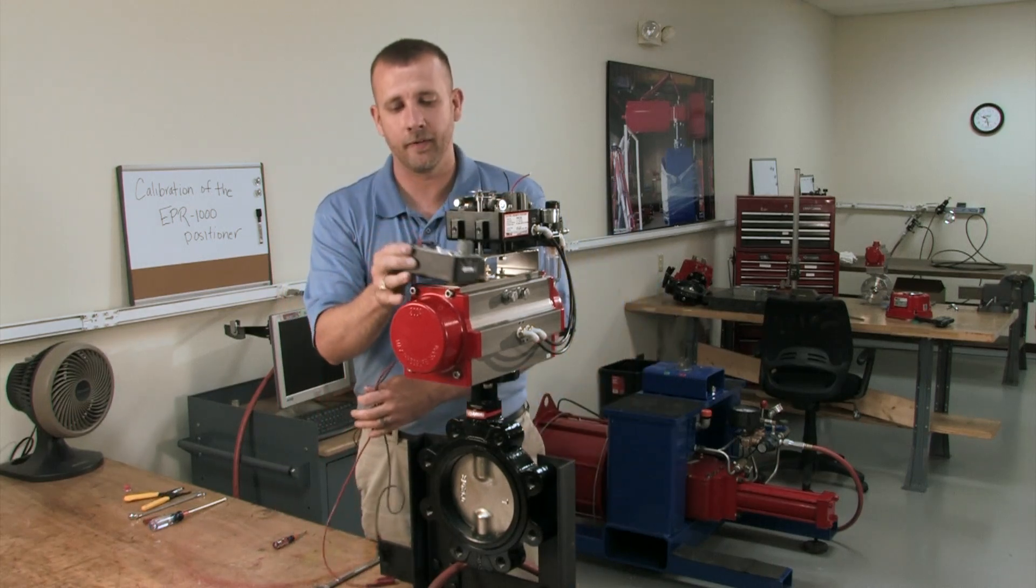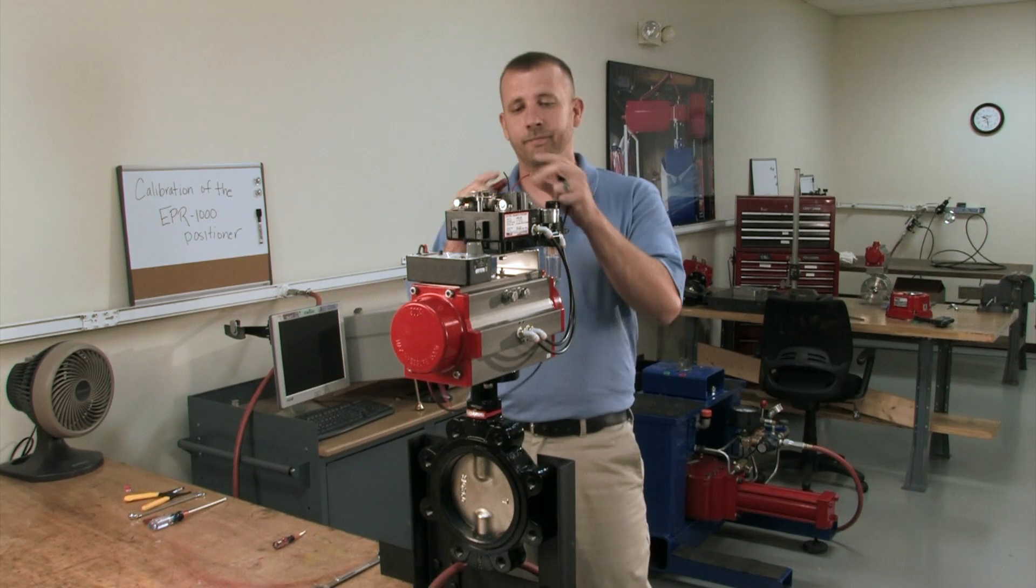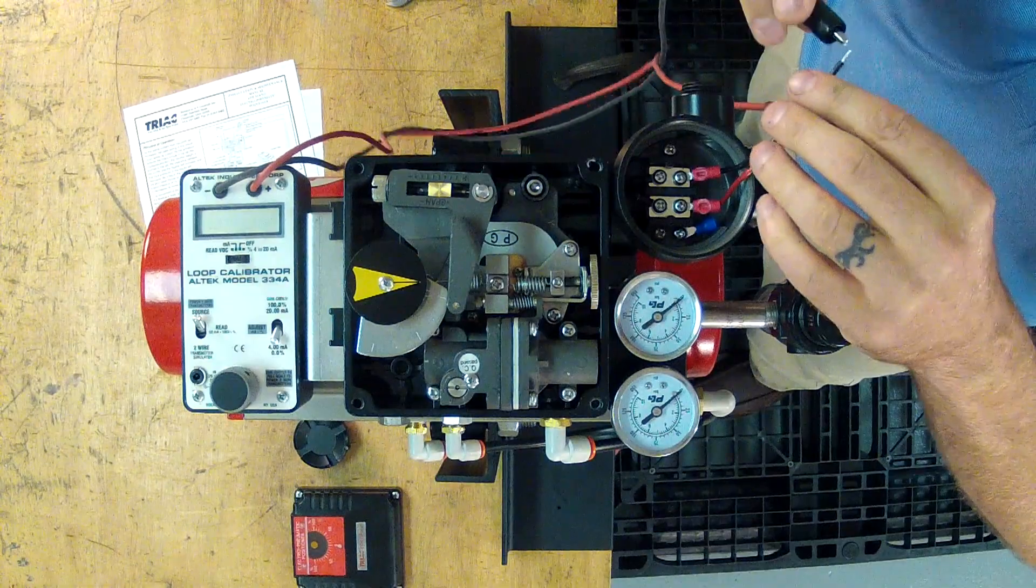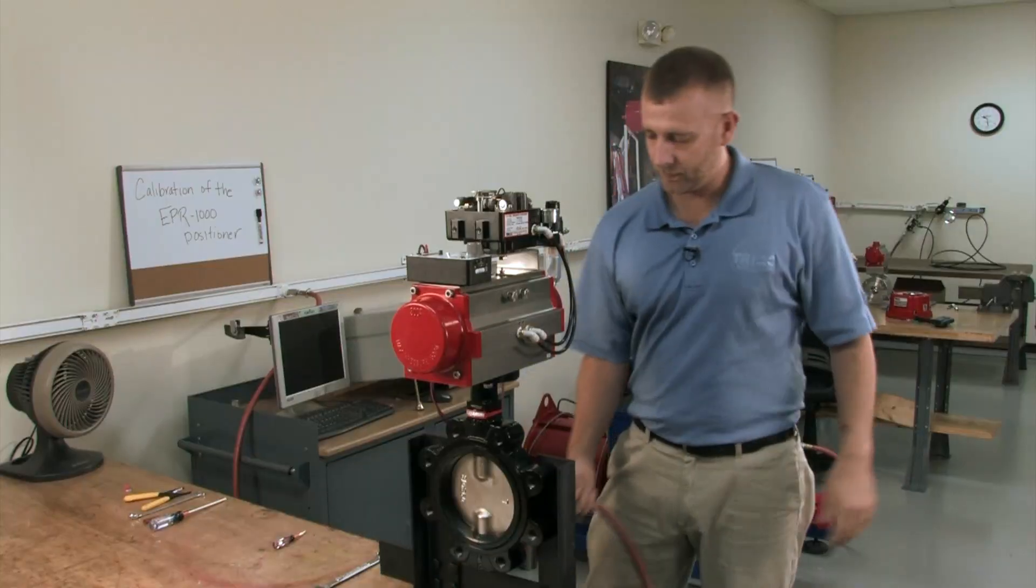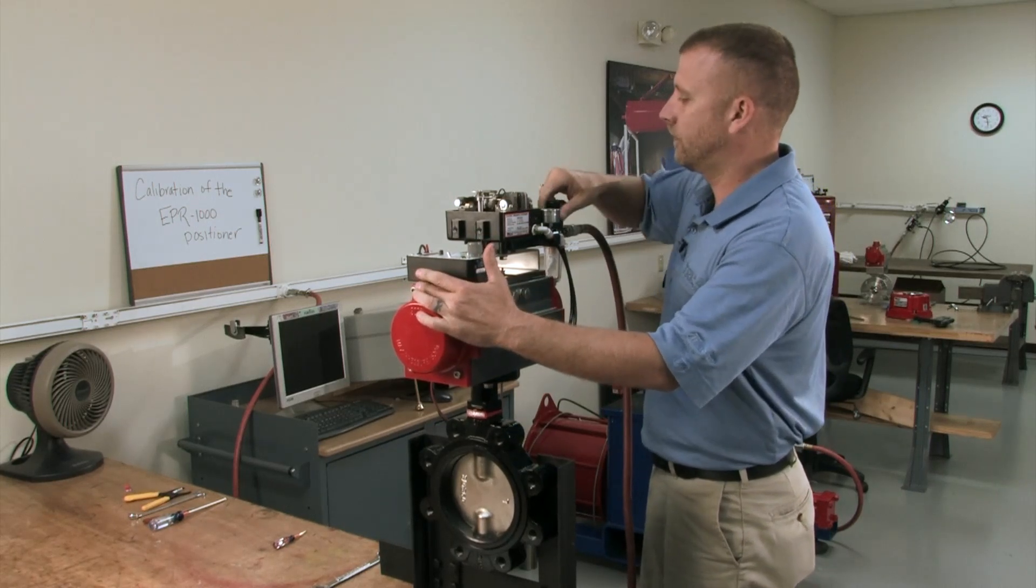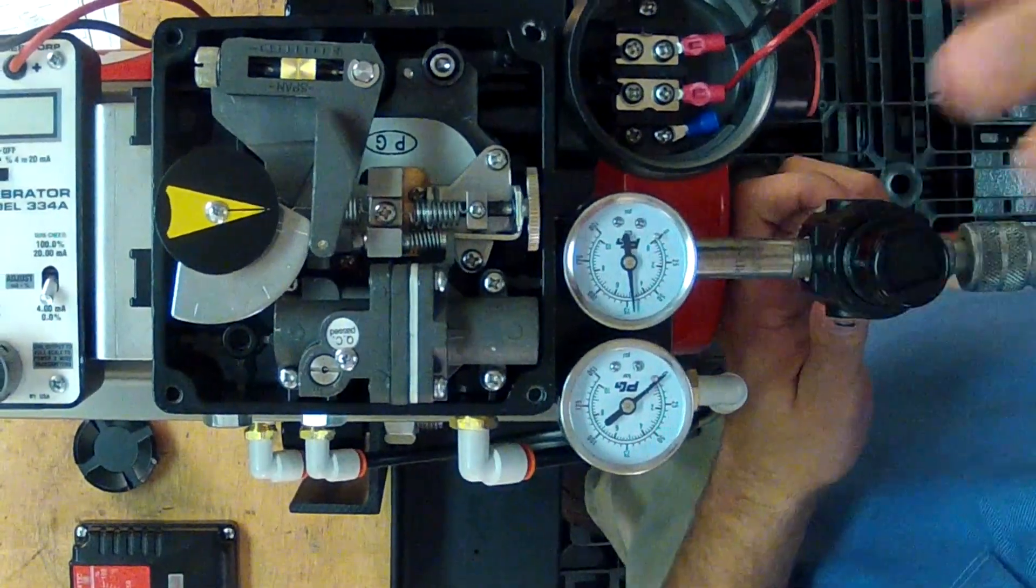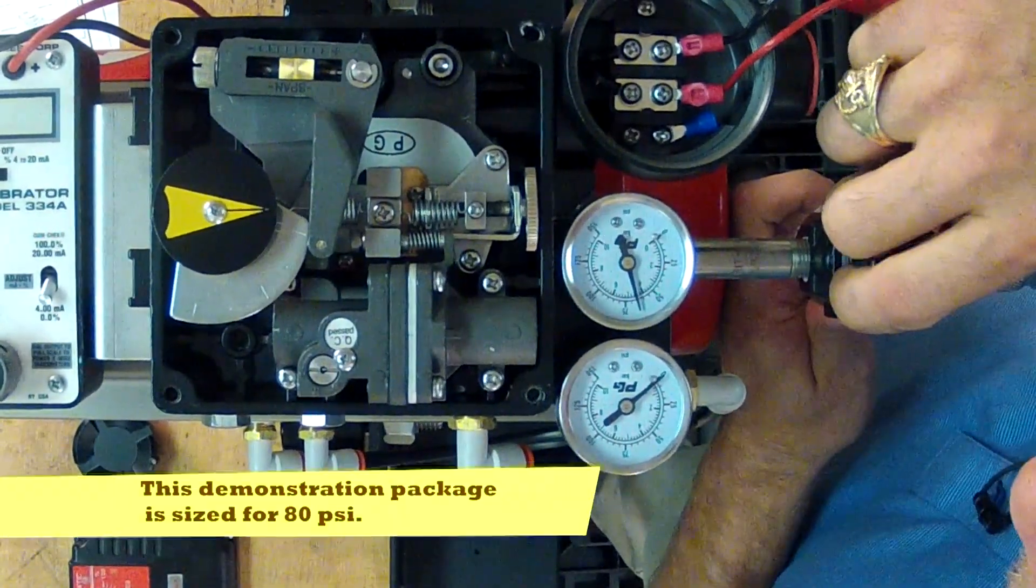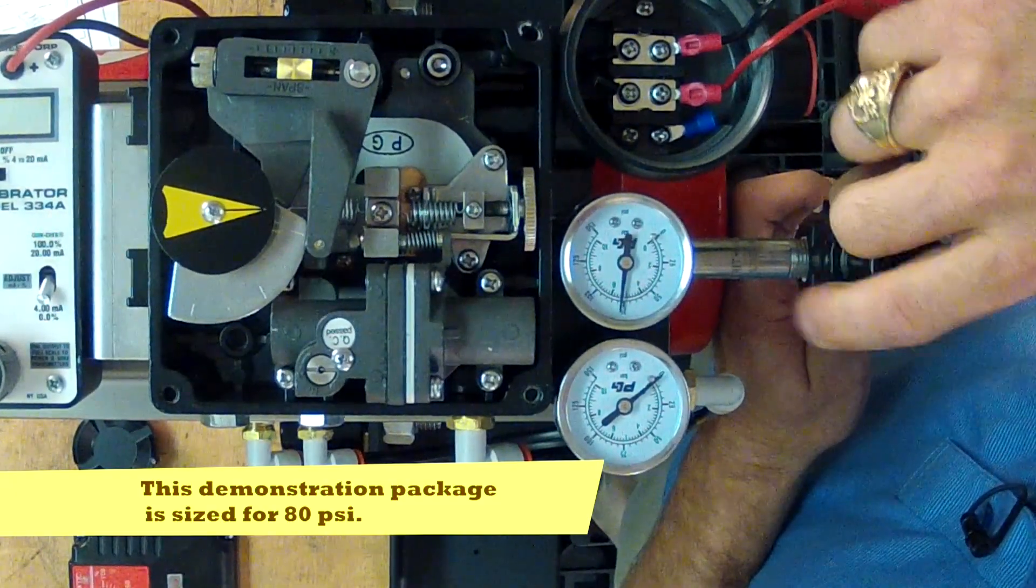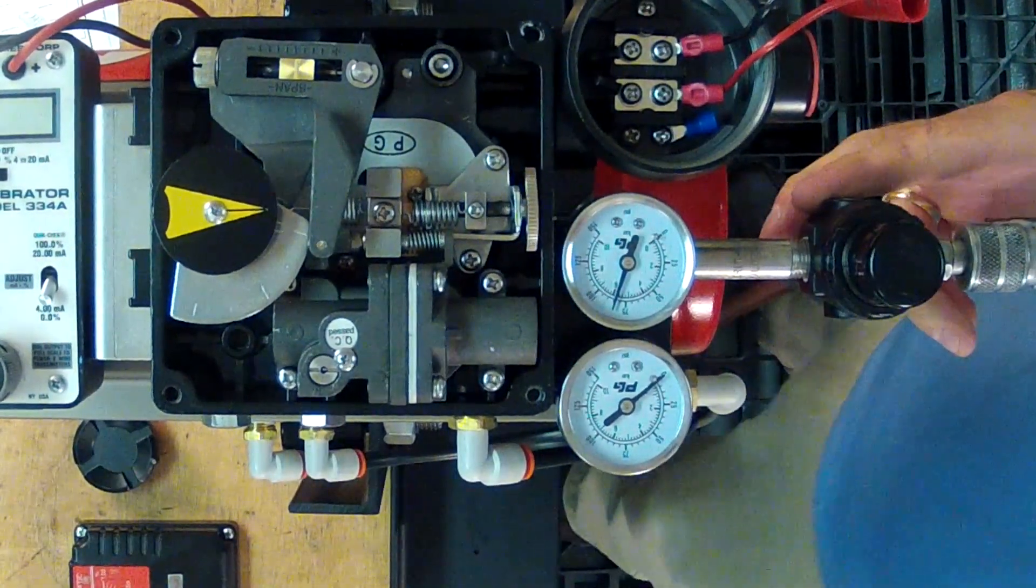4-20 milliamp handheld calibrator. Positive and negative. Now, I'm going to introduce the air on the actuator. We want to set our regulator to approximately 80 PSI. Now, we're going to start the basic calibration procedure.